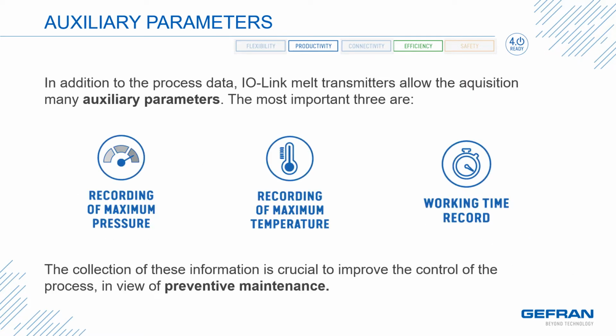And then there are auxiliary parameters in addition to process data. These are usually specific to the type of device that we're talking about, but in the case of our melt pressure transmitters, they are recording of maximum pressure, recording of maximum temperature, and recording of the working time. These collective pieces of recorded data are crucial to improve the control process and give a view into some preventative maintenance actions that could be due.